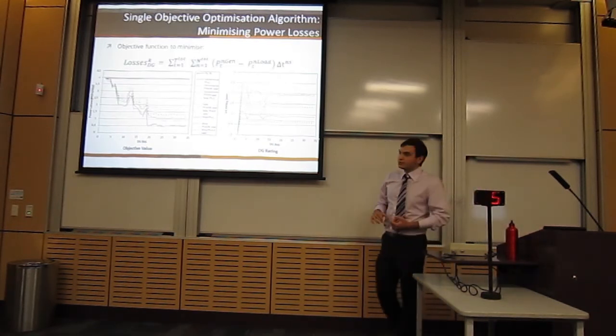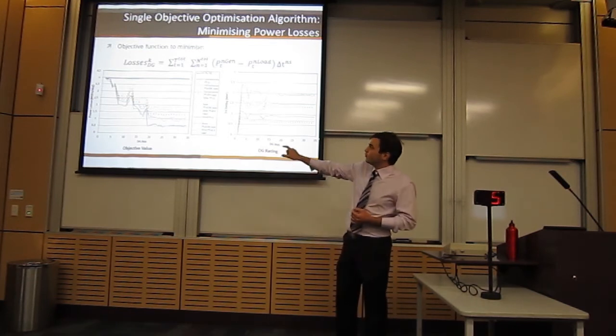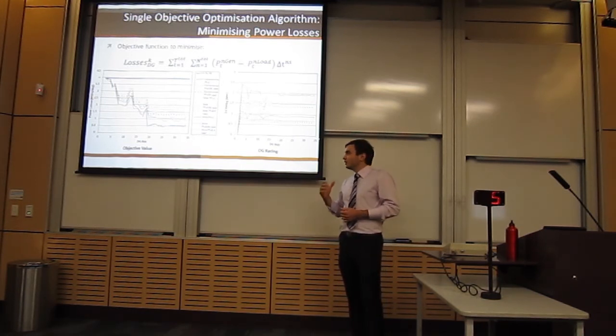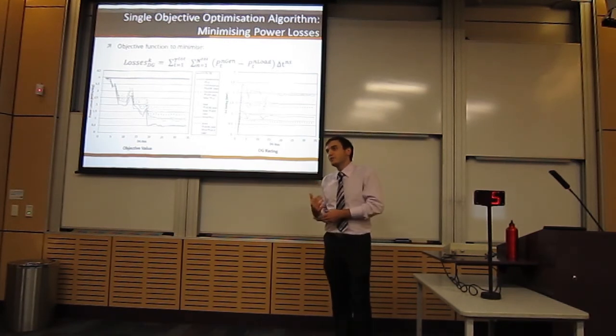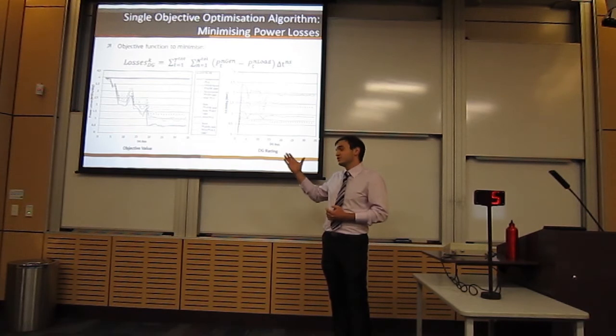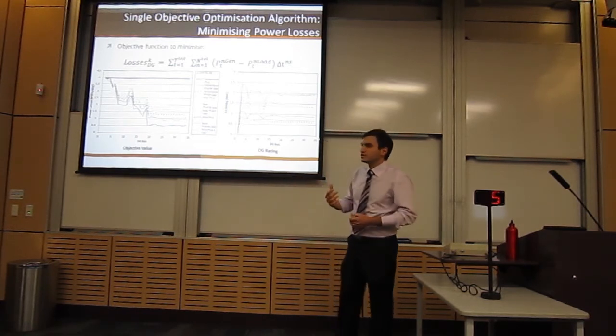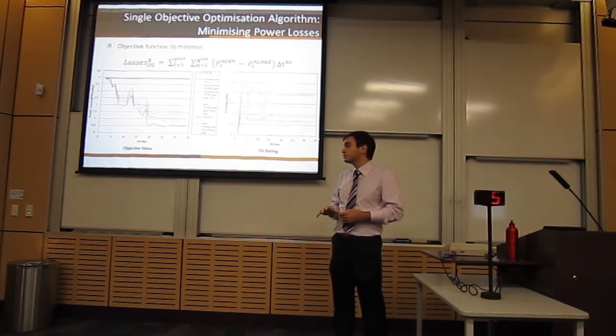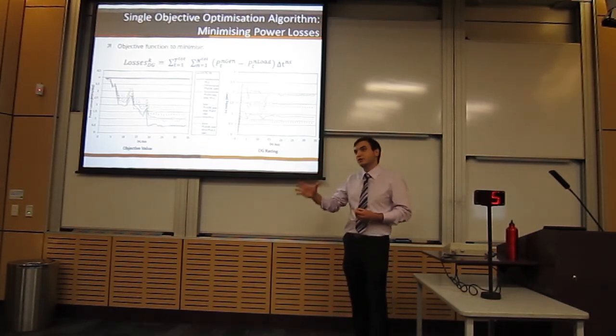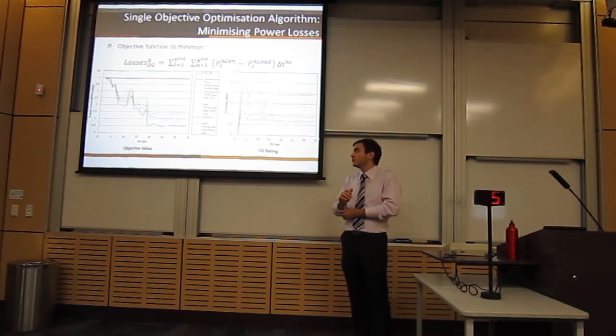The third optimization developed was to minimize power losses. Where DG is implemented after SVR2 — the second step voltage regulator, between bus 19 and bus 34 — the most substantial reduction in power losses can be achieved. This is most prominent with conventional and wind generation, with reductions of up to 85%, and solar reductions of approximately 50% to 60%. This is because a large portion of the load is aggregated at the end of the feeder; by implementing DG close to the load buses, power does not have to flow from the grid connection through upstream transmission lines where losses occur.